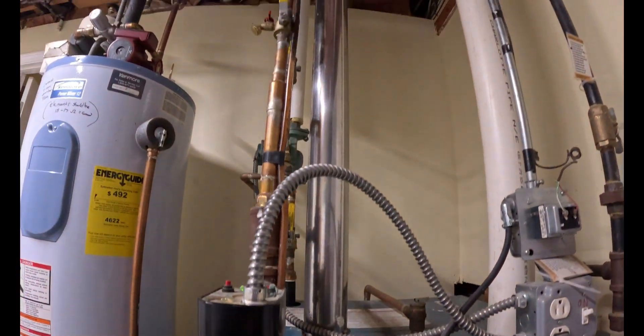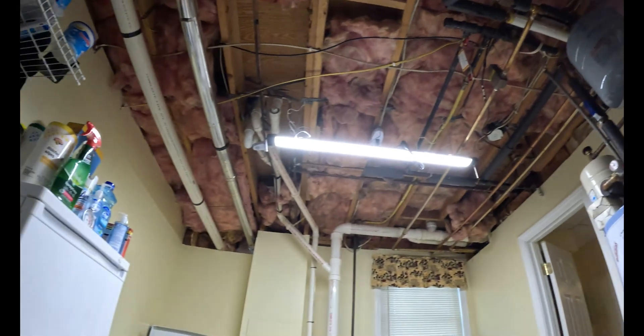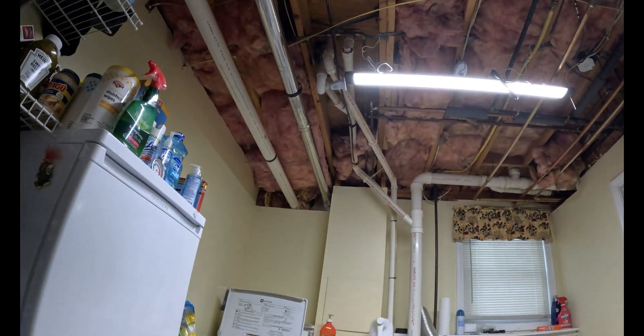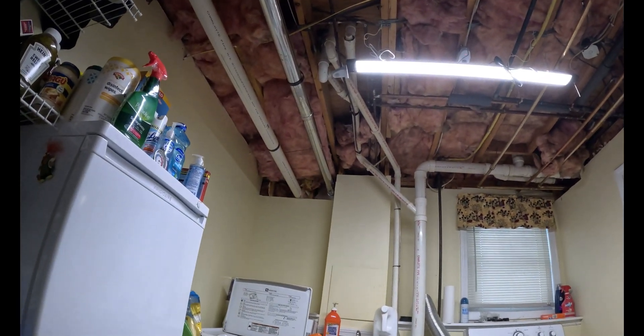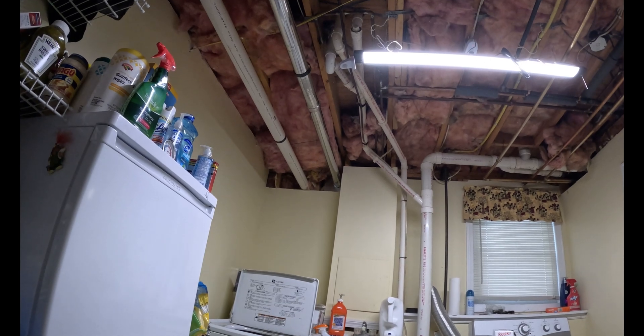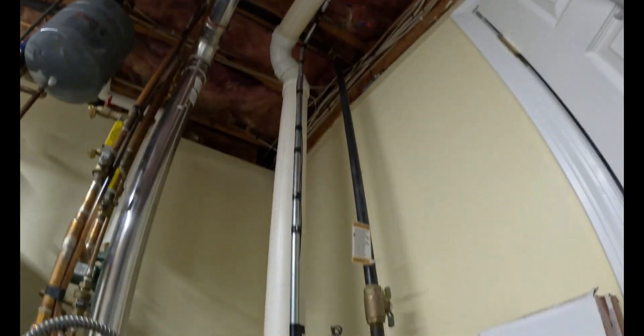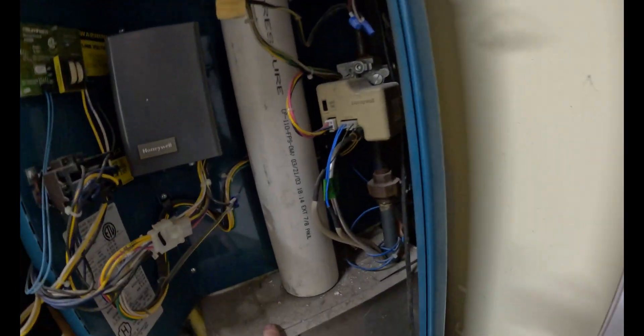This is a stainless steel vented boiler, so you see the pipe going right up here, goes up overhead and outside. So you got your vent on the right, stainless steel, three inch PVC on the left for your fresh air intake, which comes back to the boiler down and into your sealed combustion compartment.